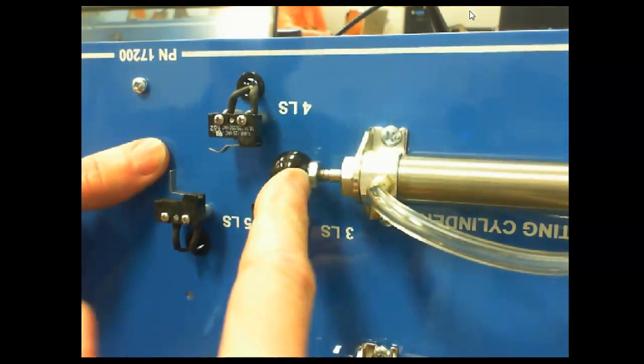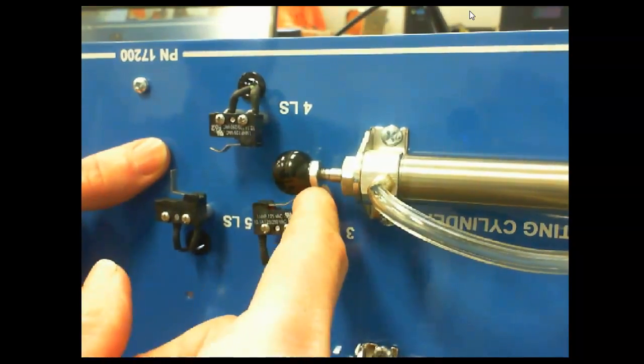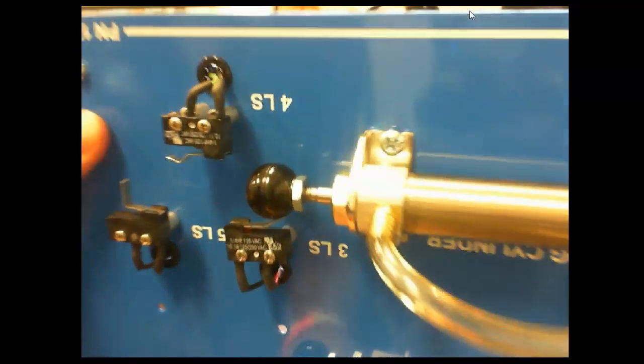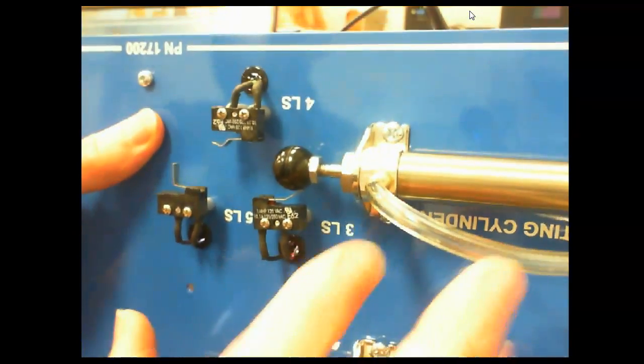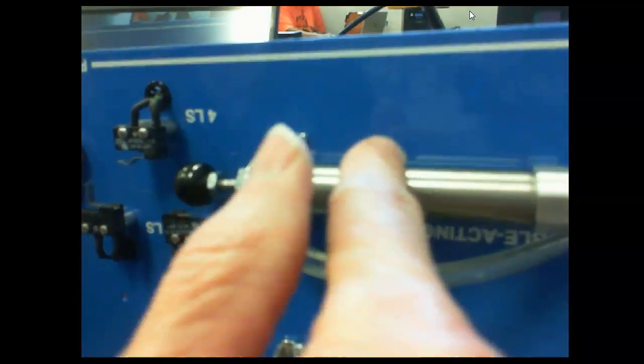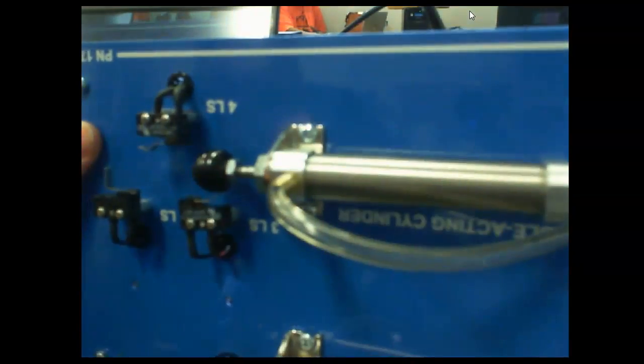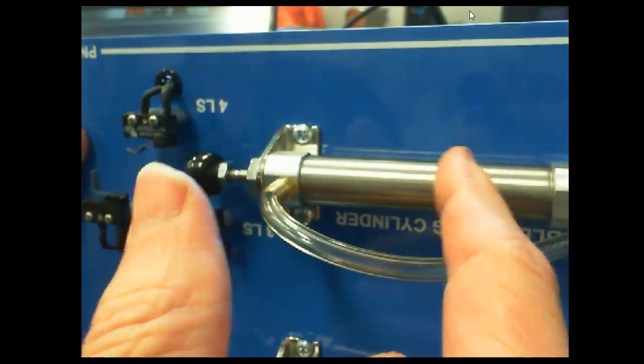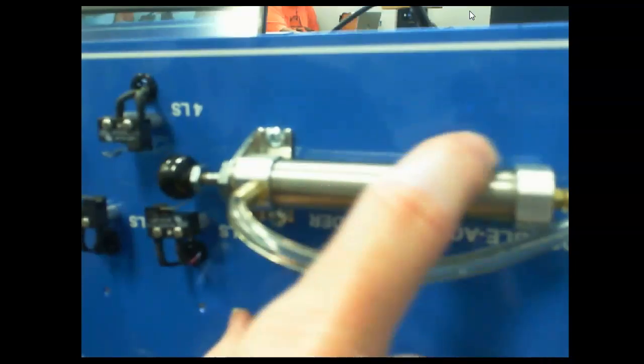On this one, they just have this ball on the end of the piston, but we'd actually make that thing strike these limit switches when it moved, when it was actually doing the work. We still have to do this kind of stuff on hydraulics, because the cylinders themselves have to be made out of a hard metal, like steel. What's nice about pneumatics is we don't run those at extremely high pressures. So a lot of your cylinders are either plastic or aluminum.